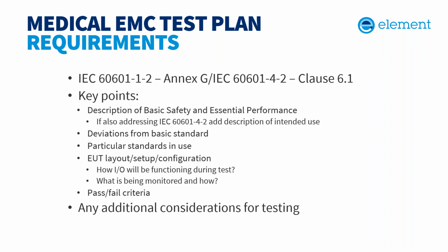So an example, think of an ablation generator. There's a risk if it turns off during a procedure, so testing should likely be done with ablation active. But on the other hand, the risk of harm is even higher if it turns on when it isn't supposed to. So you really should be looking at two different use cases to maintain that basic safety and essential performance, and then potentially a third test run to look at the intended use under 4-2. So these are all things you need to look at during your risk analysis and risk assessment to see what makes sense, what should be required, what is going to prevent harm, and address these risk factors.